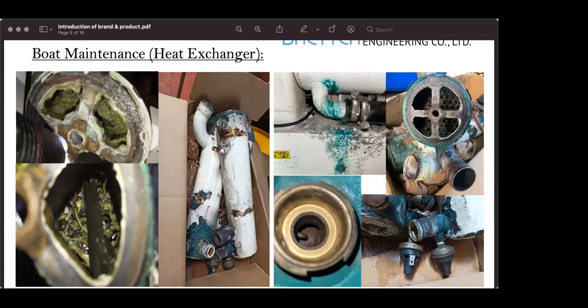Is there any pressure sensor that gives an early warning there's something wrong? The pressure sensor is funny. When it's lower, it tells you it's out of coolant, loss of coolant. There's a sensor for when it's lower, telling you to replace the impeller. But they don't have a sensor for higher pressure, you have to clean the heat exchanger because they may expect you to do that as standard maintenance, every 2 years, like you're saying.